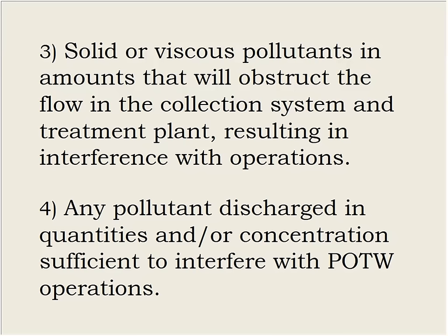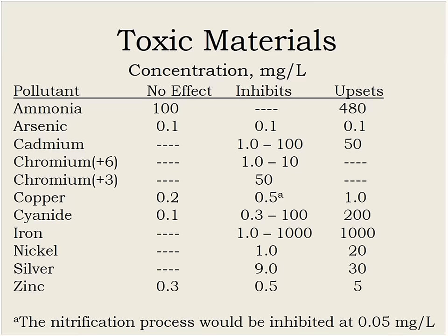Well, cleaning things up. Any pollutant discharged in quantities or concentrations that will interfere. Again, metals, certain organics, can't be discharging that down there. It interferes with the process. Some metals primarily are the biggest problems. Cadmium, you start to inhibit the process at one part per million. You're into a total upset at 50. Nickel's pretty low too. Zinc, half a part per million. Doesn't take a lot to really mess up the bugs. They don't like that stuff. So that is prohibited.